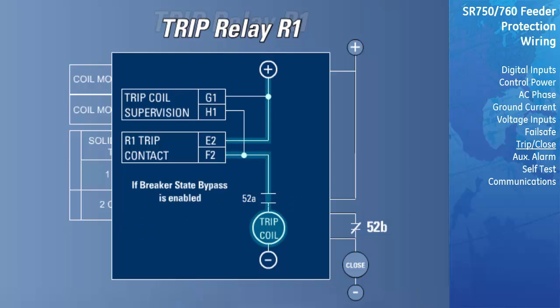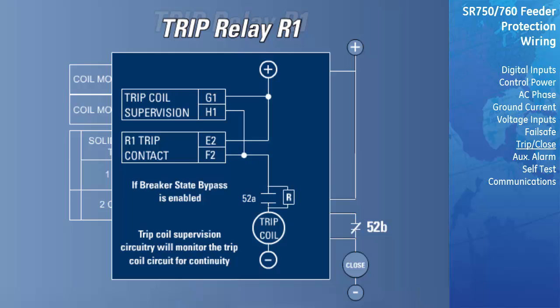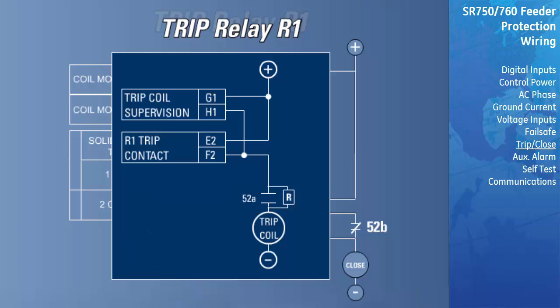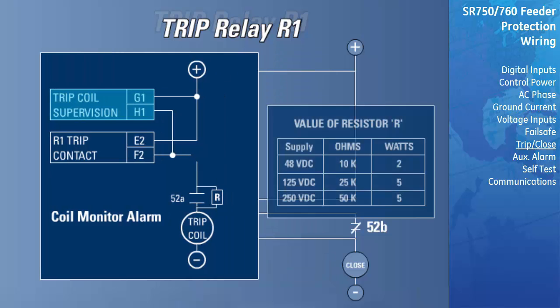If trip coil supervision is enabled and the breaker state bypass option is selected, the coil supervision circuitry will monitor the coil circuit for continuity at all times regardless of breaker state. This requires the installation of a resistor to create an alternate path around the 52A contacts in series with the trip coil when the breaker is open. If that continuity is broken, a coil monitor alarm will indicate a failure in the trip or close coil circuitry. The chart shown gives suggested values for the resistors depending on the control voltage used.